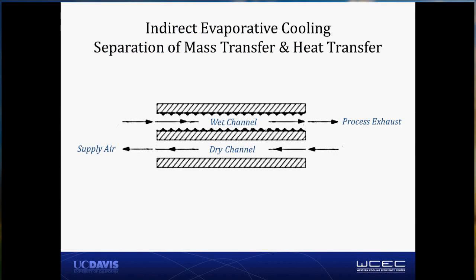The primary path remains dry, and it usually brings air in from outside or perhaps some other source, and that air is cooled down as it passes through the heat exchanger. The cooling effect is occurring because of evaporation, but that evaporation is occurring in a secondary channel, which is wetted, and effectively the heat exchanger separates the heat transfer and mass transfer processes.